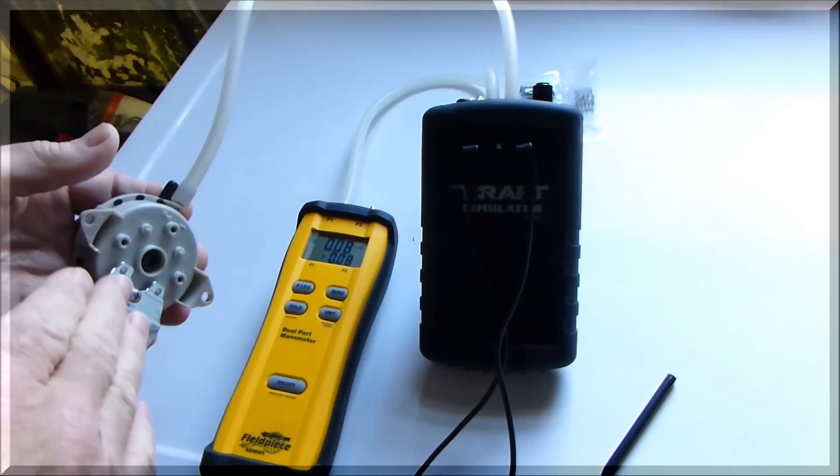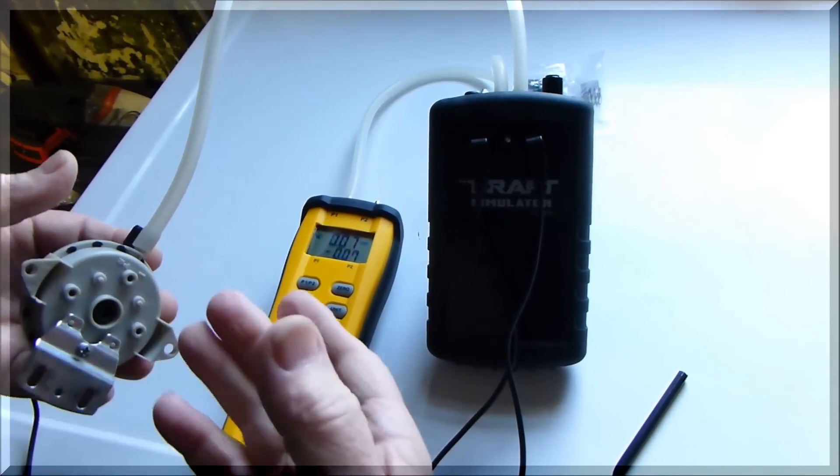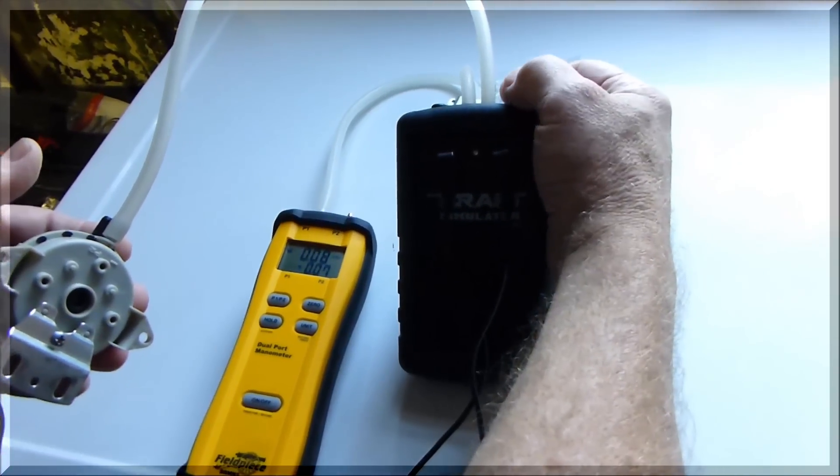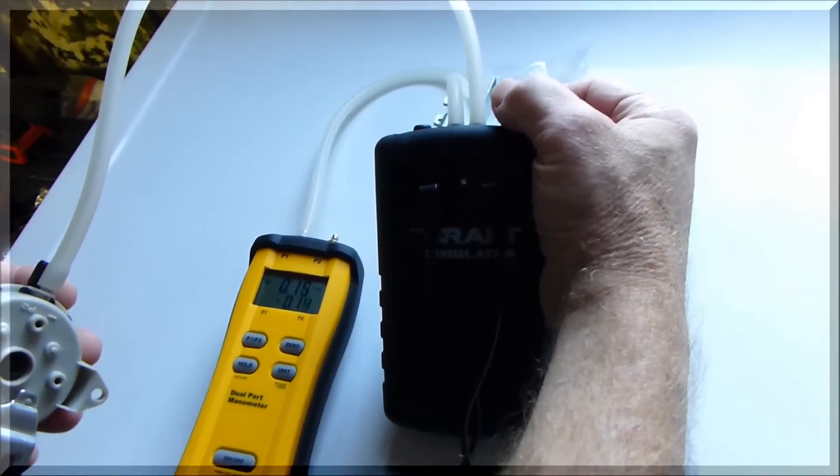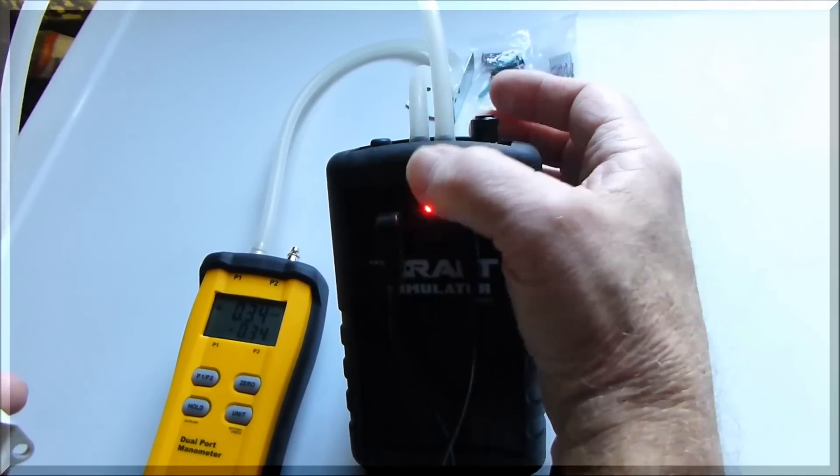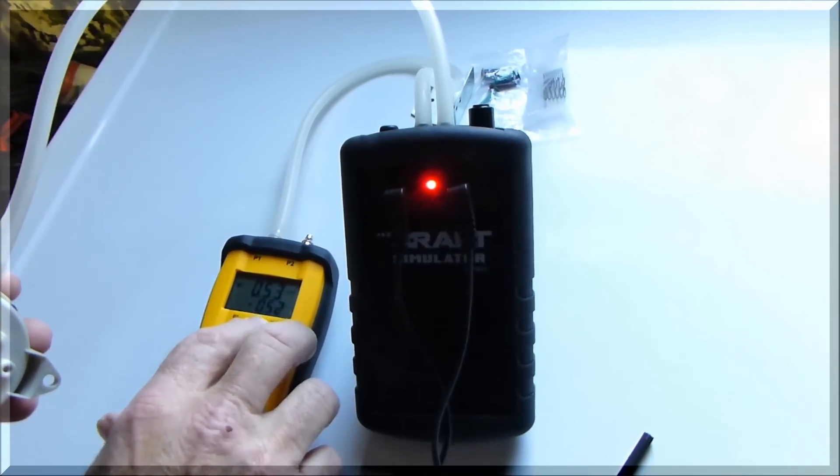Now since we're calibrating this, we're going to adjust our pressures up to where we want this to go. We're going to turn this in clockwise to change the pressure to the reading that we want it to be. Notice the LED came on, doesn't matter at this point. We're going to take this up to a .80.